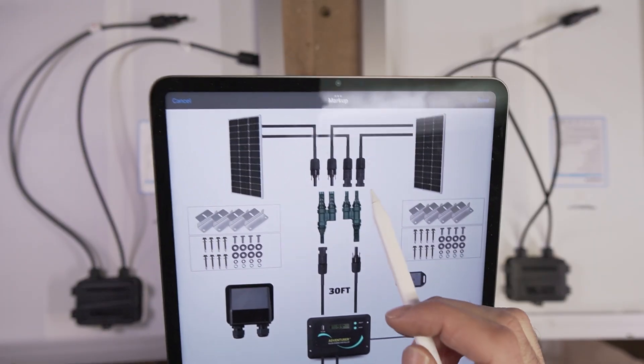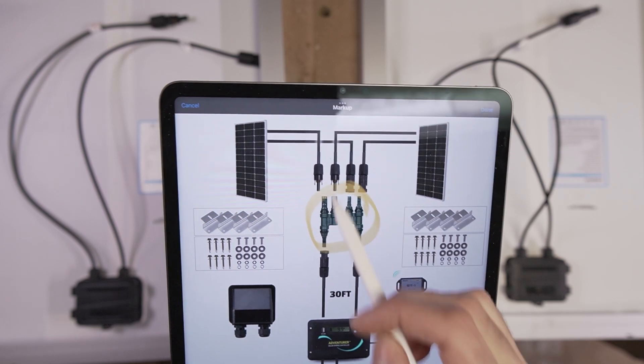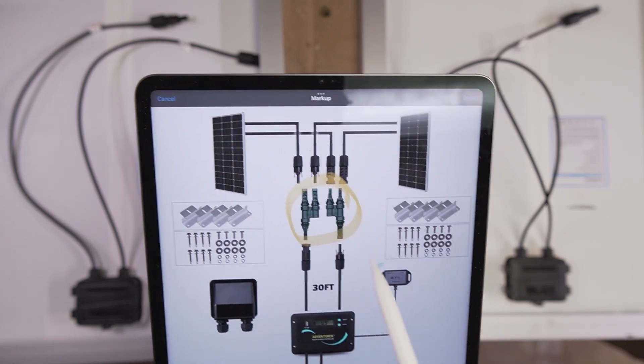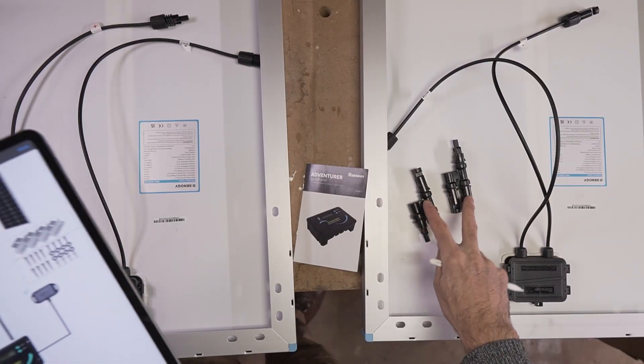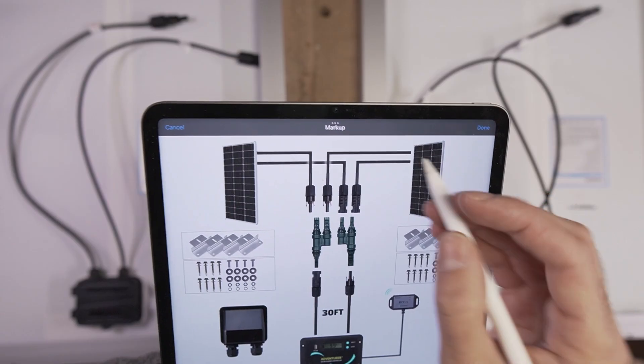The disadvantage of running panels in series is that if one panel is shaded, it's going to degrade the performance of the entire solar array. But one of the advantages is you can run longer runs of wire at higher voltage. The other option is to wire it in parallel using these Y connectors right here.